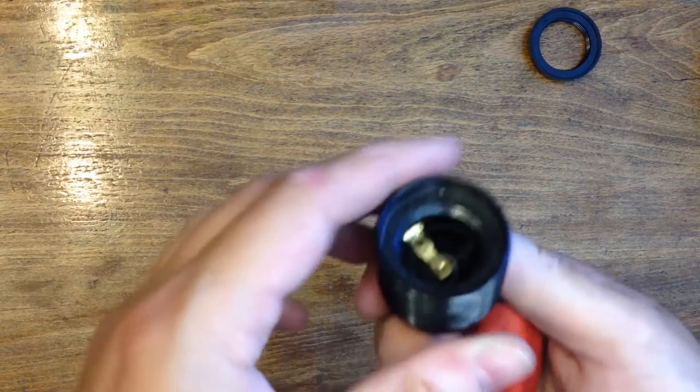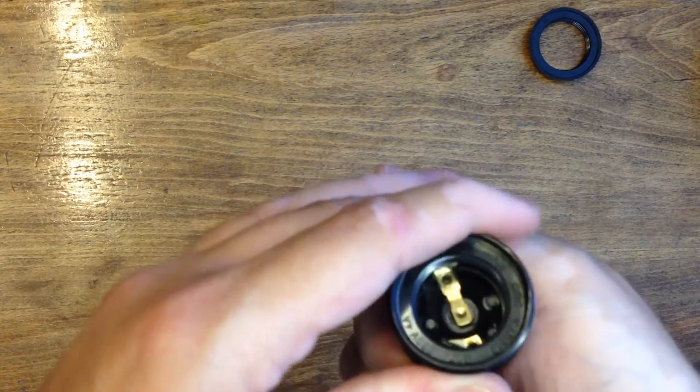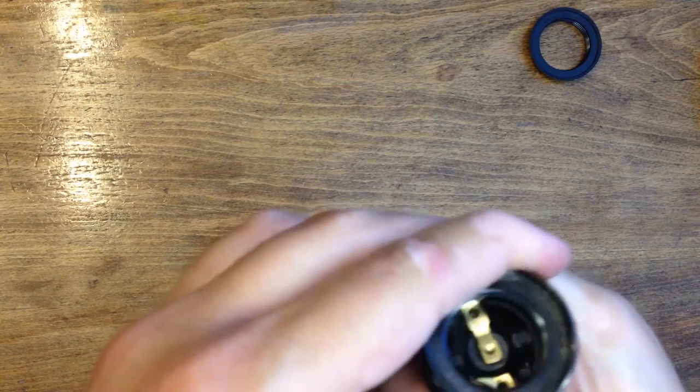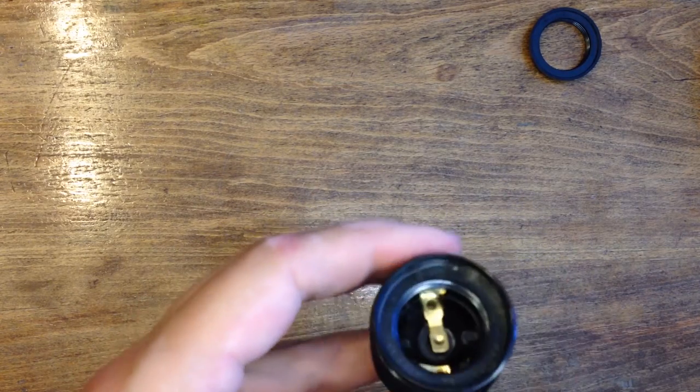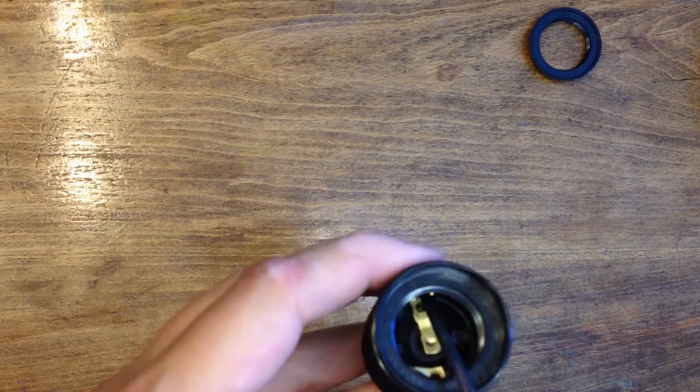In order to unlock a lamp holder, locate the center terminal that goes to the edge of the bakelite socket. Press down on the edge with a screwdriver. You may have to press a few times to get it to unlock.